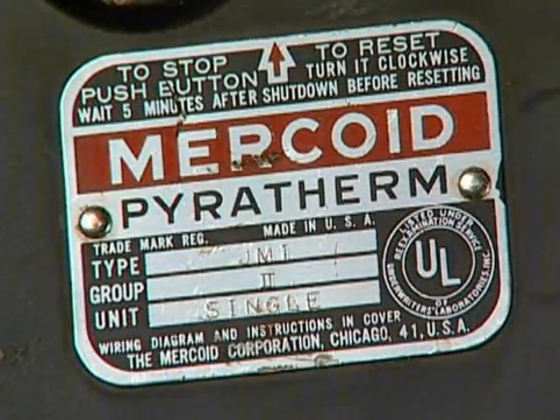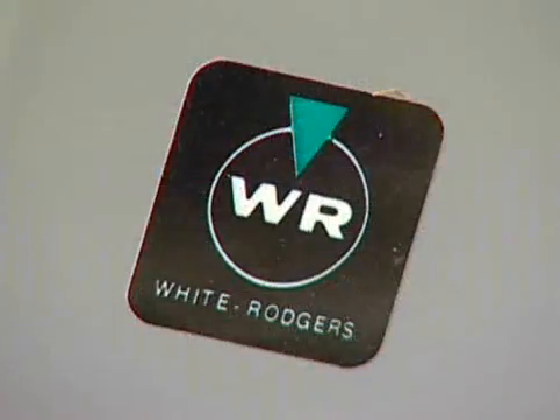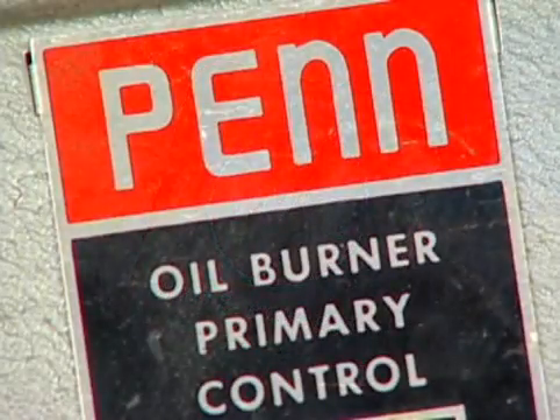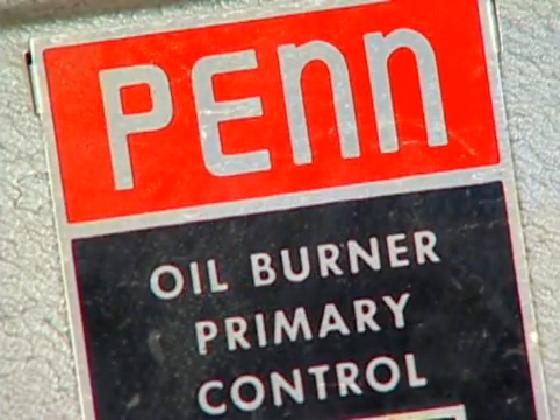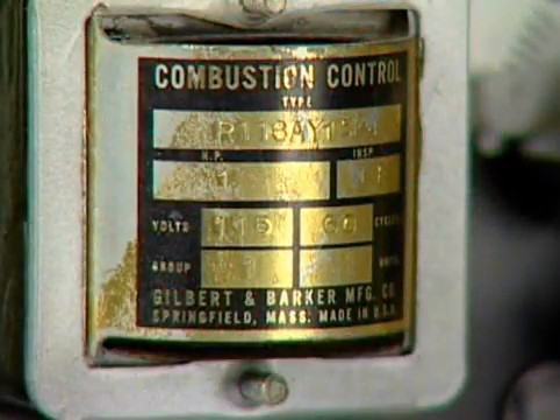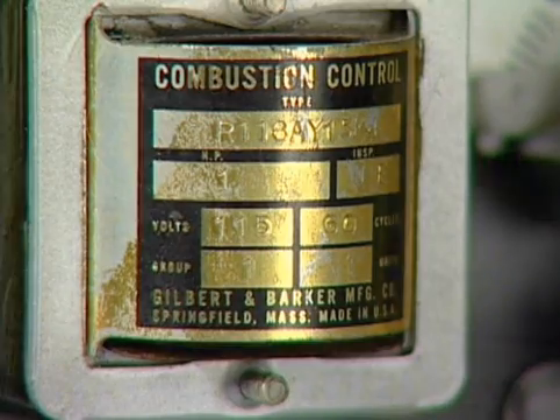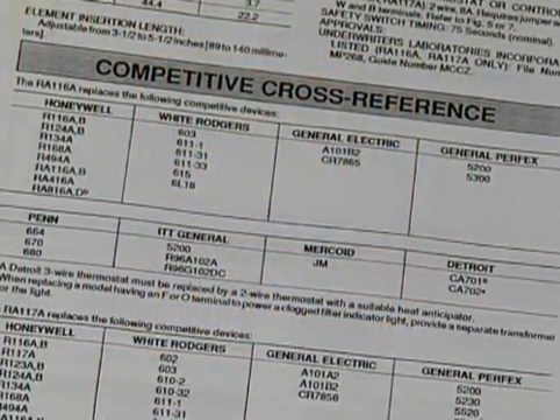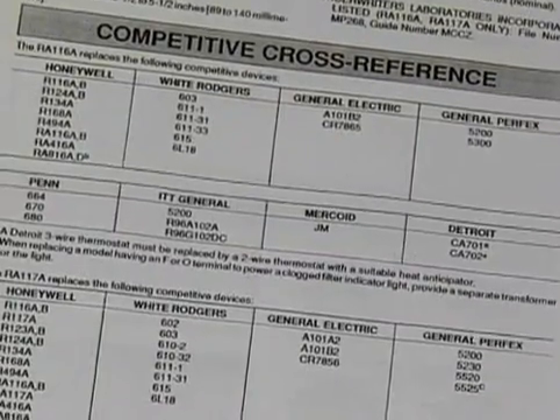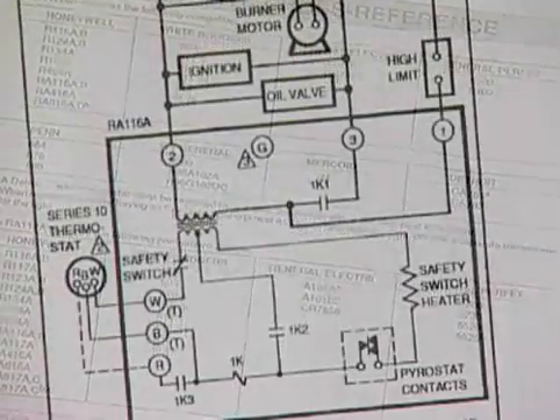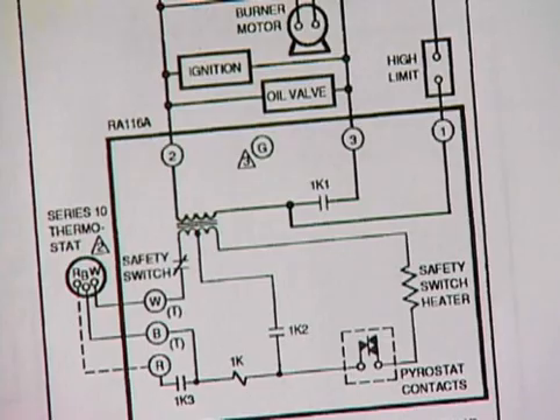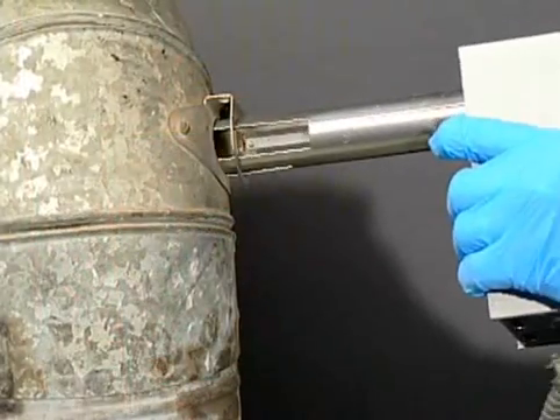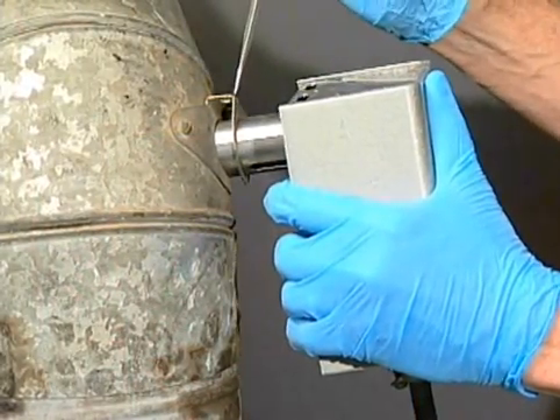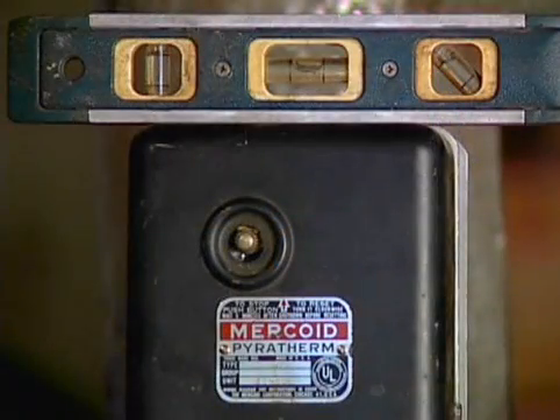There are many brands and types of these controls in the field. Some operate on line voltage only with no low-voltage circuit. There are mercury tube controls, two-piece controls, and a host of controls manufactured by companies that many of us have never heard of. Luckily, the major suppliers of thermomechanical primary controls adopted similar standards, so basic wiring is the same, regardless of the make and model. Mounting instructions are also similar for all stack relays, except those containing mercury tubes, which must be mounted level.